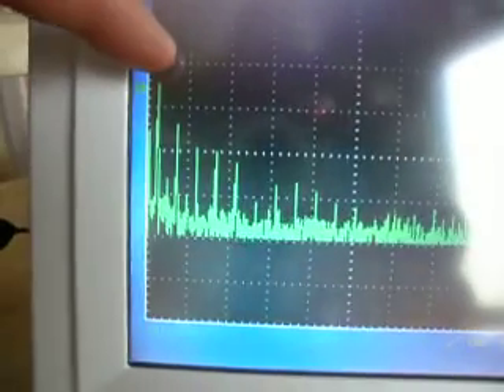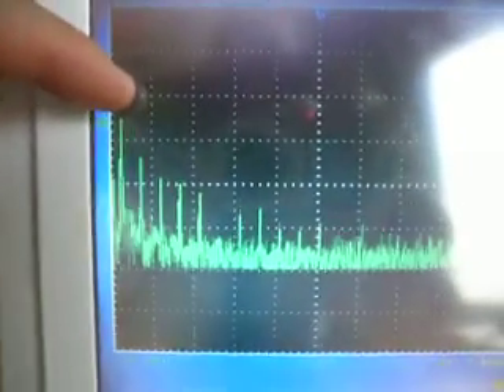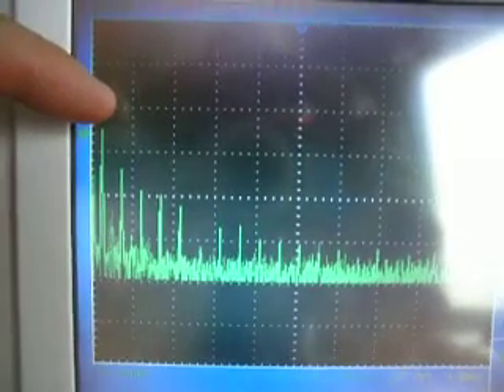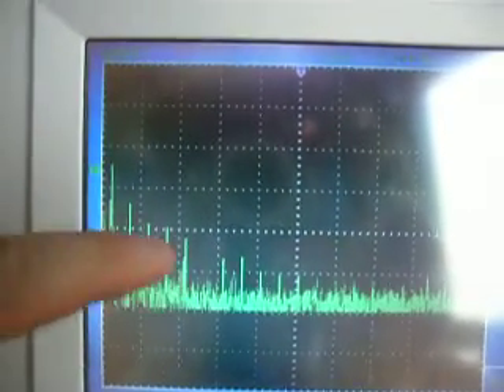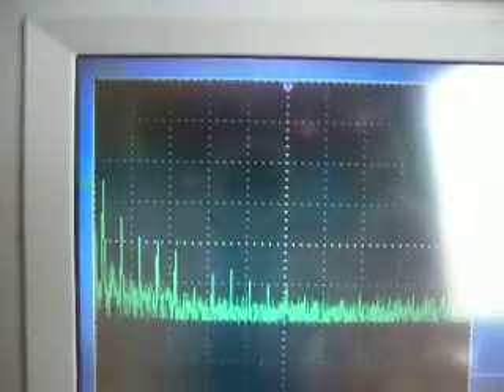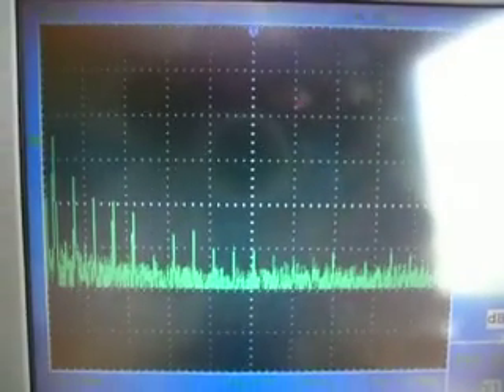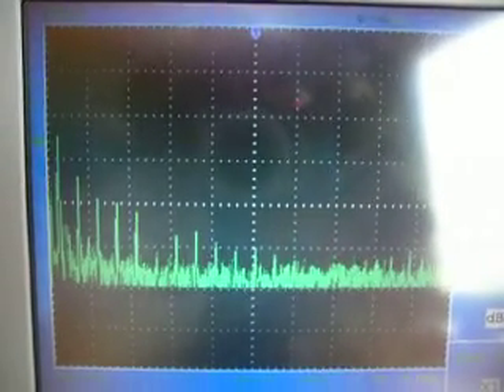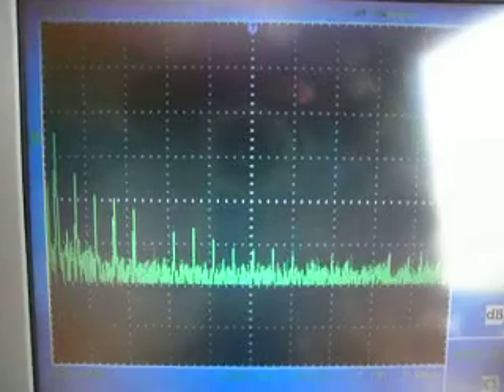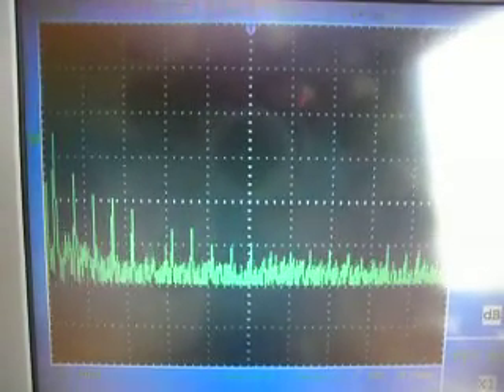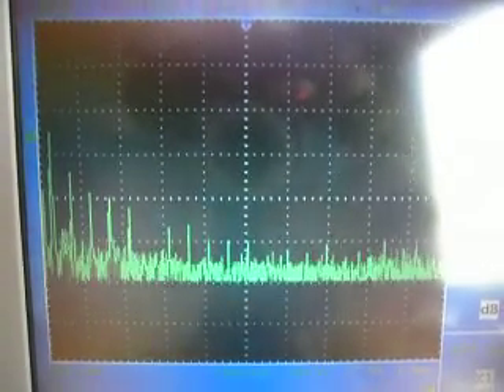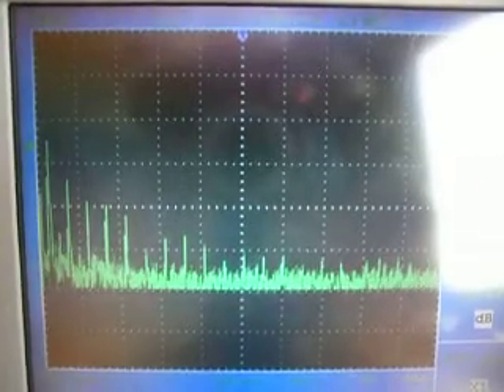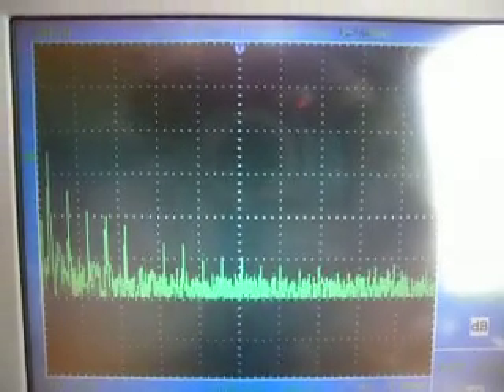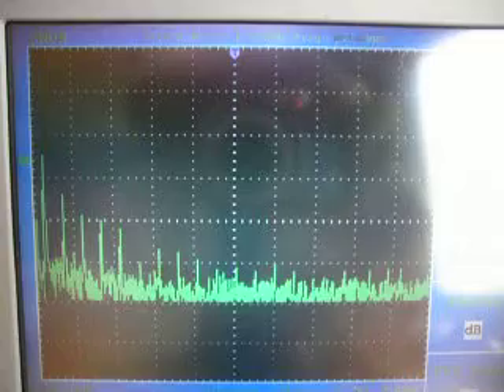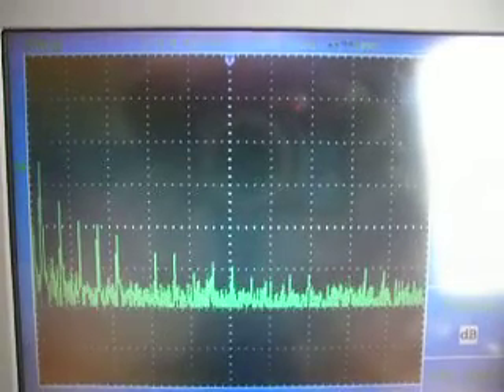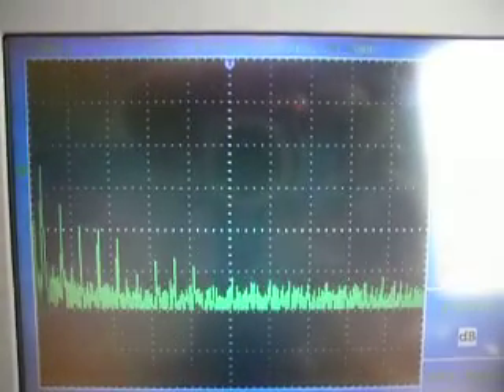This big spike over on the left is the mains frequency, that's 60 Hertz. These other big spikes tailing off are known as the harmonics, a repeating 60 Hertz frequency. What we can see is the odd harmonics, which is quite typical of a utility system. All that flickering down on the base is just electrical noise on the system. It's a very noisy electrical system we're measuring right now.